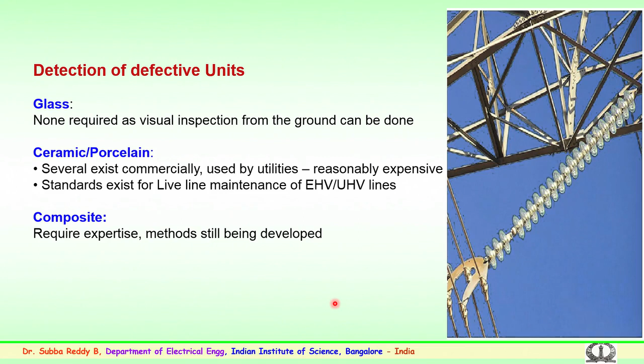Among the electrical methods, the techniques employed are field measurements. It could be using sensors. The voltage distribution method is normally conducted in the laboratories, where the voltage is measured across each disc in a string and the percentage voltage distribution is found out. It could then be seen which insulator in the string is faulty, and that this particular one has to be changed. Similarly, there is the insulation resistance method for finding out faulty insulators in the string.